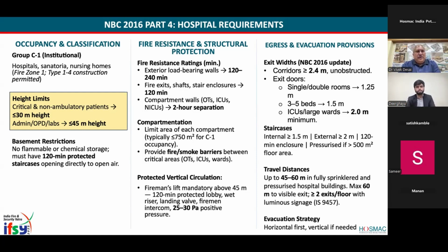Then there are certain basement restrictions. I think we should follow these religiously. No inflammable or chemical storage in the basement, because if it burns, then there is a problem. All staircases should have 120-minute protection, opening directly to the open air when you go through, basement up. Fire resistance in terms of structural ratings: load-bearing walls 120 to 240 minutes. Fire exits, shafts and staircases, 120-minute fire rating. Compartment walls, 2-hour separation rating. Limit the area of each compartment, typically to 750 square meters for C1 occupancy. This was earlier 500 square meters, but if you are a completely sprinkled and fire-detected safe building, they allow you to go 50% more. So that kind of compartmentalization is allowed.